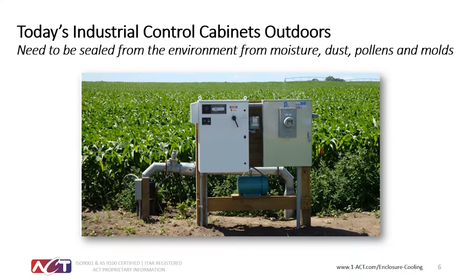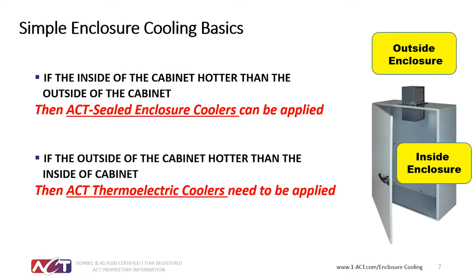Fortunately, advanced cooling technologies provide sealed enclosure coolers that effectively protect sealed cabinets from external contaminants and moisture. ACT's line of heatsink and heat pipe-based coolers are sometimes referred to as heat exchangers. ACT's sealed enclosure cooling heat exchangers offer excellent thermal management for sealed enclosures where the air temperature on the inside of the enclosure is hotter than the air outside the cabinet. These applications are referred to as above ambient cooling. The reverse case, where the air temperature is hotter on the outside of the cabinet, requires subambient or active cooling. ACT offers thermoelectric solid-state air conditioning systems to meet this need.